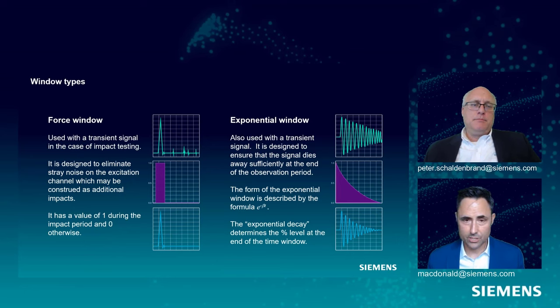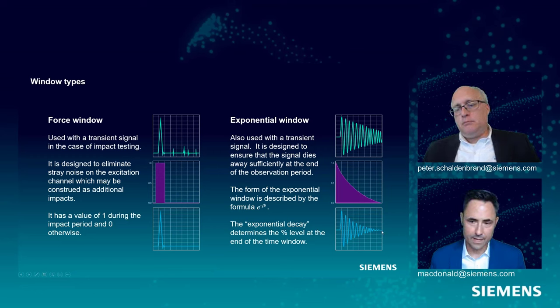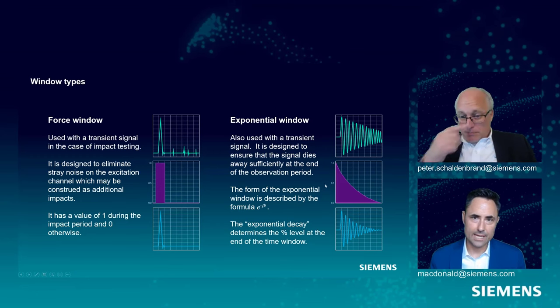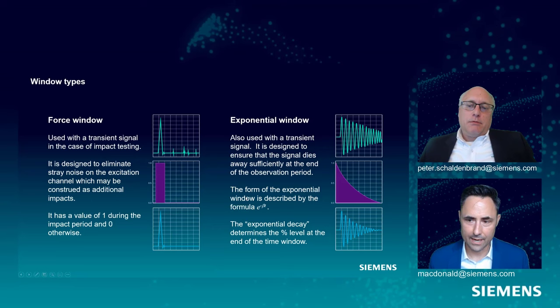Some other types of windows you can use. Force window, again, impact testing where we have an impact hammer. We are really interested in this impulsive part of our force, maybe about setting down the hammer. We don't want to have any of this little noise on there, and so a force window is essentially one during the impulse event, and then off for the rest of it, and we end up with this nice clean impact event, and then no signal noise. It's going to help us get a nice leakage-free impact signal, and it's often paired with an exponential window, which we'll use to force a signal that's still oscillating by the time we come to our end of our observation window. We're just going to sort of artificially damp that vibration out, so it's zero at the beginning and zero by the end. And this exponential decay artificially adds some damping, but we know what we're applying. We can back that out after the fact.